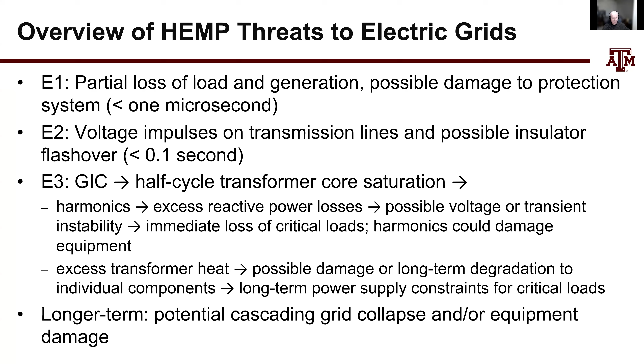Then E3, which is the focus here, impacts the grid by causing geomagnetically induced currents, or GICs. Those GICs can saturate transformers, which tends to increase reactive power loading on the grid, causing harmonics that further increase reactive power loading, and you could get a voltage collapse as a result. There's also potential for transformer heating due to the harmonics. Longer term, we could have a potential for cascading grid collapse and/or equipment damage.